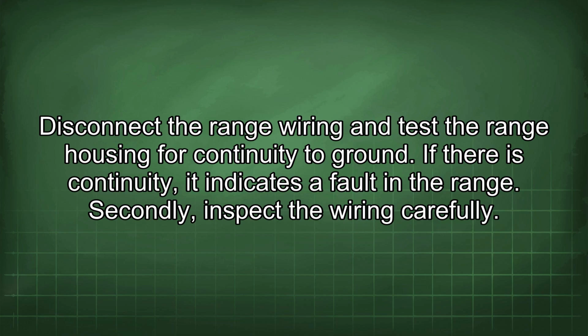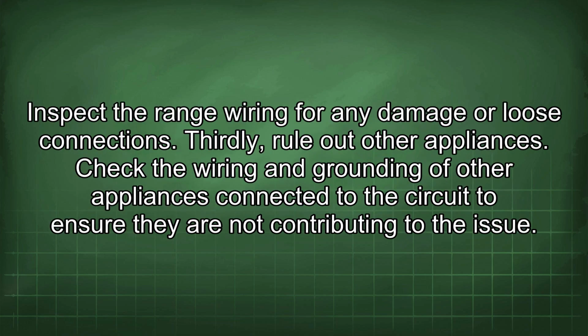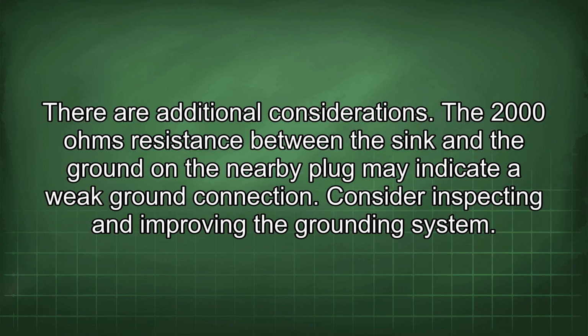Secondly, inspect the wiring carefully. Inspect the range wiring for any damage or loose connections. Thirdly, rule out other appliances. Check the wiring and grounding of other appliances connected to the circuit to ensure they are not contributing to the issue. There are additional considerations. The 2000 ohms resistance between the sink and the ground on the nearby plug may indicate a weak ground connection. Consider inspecting and improving the grounding system.